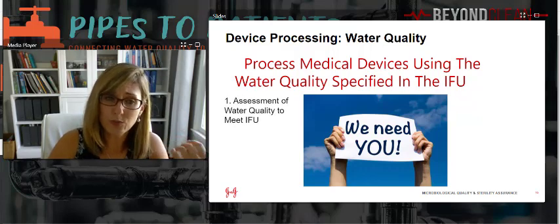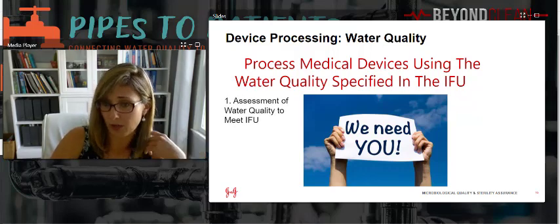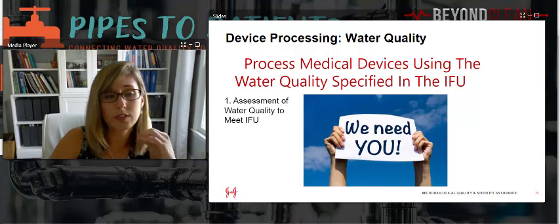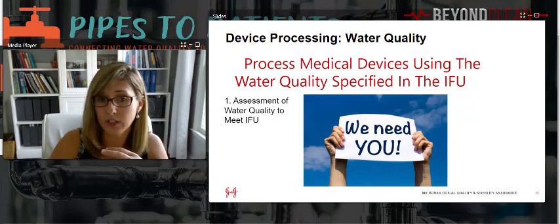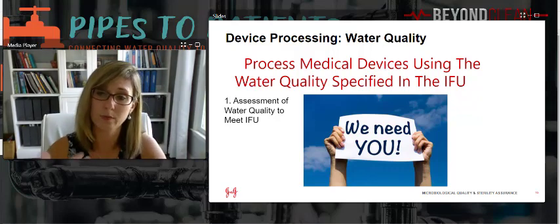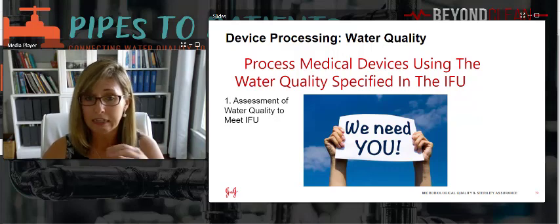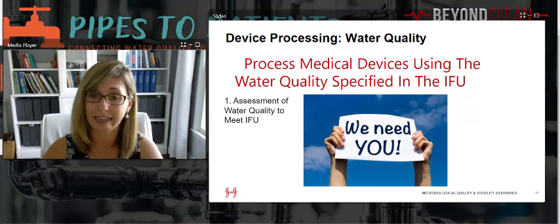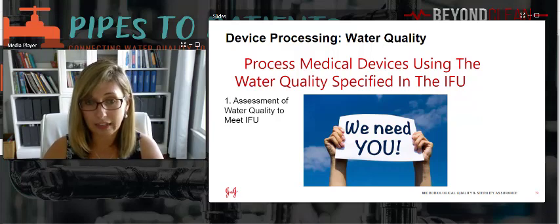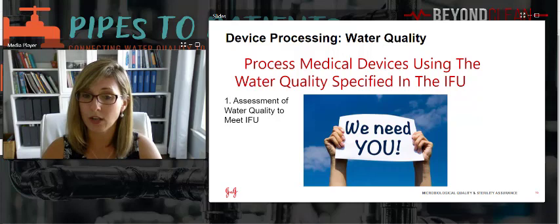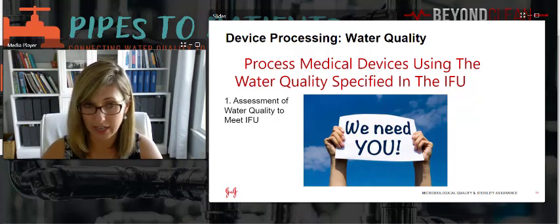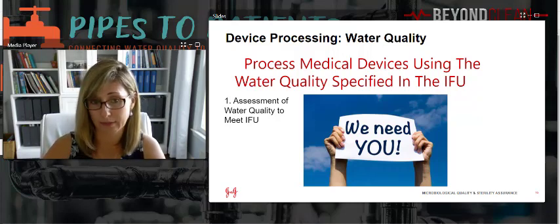So the first is the assessment of the water quality to meet the IFU. So this is typically the water maintenance personnel at the healthcare facility that performs this assessment of the quality. And it starts with the tap water that comes from the public utility source that's analyzed usually by an accredited facility or within the test laboratory with specific analytical equipment that has the expertise in water quality to determine what the water quality is, and if so, what is the type of treatment.